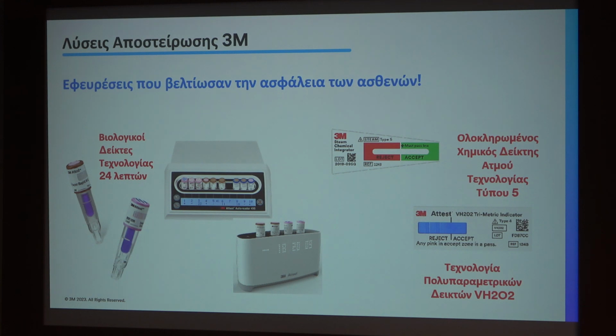And of course, it's not only the indicator, they come with readers. Especially after 2003, there were more improved systems like fluorescent technologies, so you don't have to wait 48 hours. It started with 3 hours, and today it is up to even 24 minutes. So fast systems are coming, because it is important to remember that it's not only the biological indicator, it's a system with an auto reader. What is the importance of monitoring when it comes to patient safety? The faster systems allow faster corrective actions if needed, not only for biological indicators, but also chemical indicators, which ensure sterilization safety at every pack.